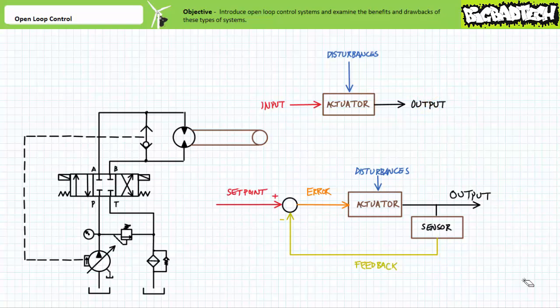All right, that's about it for open-loop control. In conclusion, this lecture examined open-loop control systems. We learned an open-loop control system is a means of process control that does not use feedback to determine if resultant output has achieved the desired goal. Consequently, while simple and relatively inexpensive, an open-loop control system cannot automatically correct for errors nor can it compensate for disturbances. Open-loop control systems require human supervision to ensure their output remains inside an acceptable range. We examined limitations of open-loop control systems when subjected to various disturbances including internally generated ones like spool position hysteresis, as well as external ones like variations in applied load, friction, temperature, pressure, flow, leakage, and more. Finally, we discussed opportunities for closure and briefly discussed the advantages of a closed-loop control system in terms of response, accuracy, and endurance.